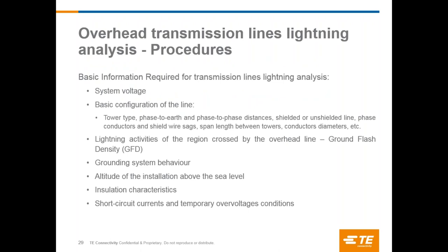phase to earth and phase to phase distance, if the line is shielded or unshielded, phase conductors and shield wire sags, span length between towers, conductor diameter, etc. Lightning activity of the region crossed by the overhead line, the ground flash density concept we'll be talking about in the next slide.